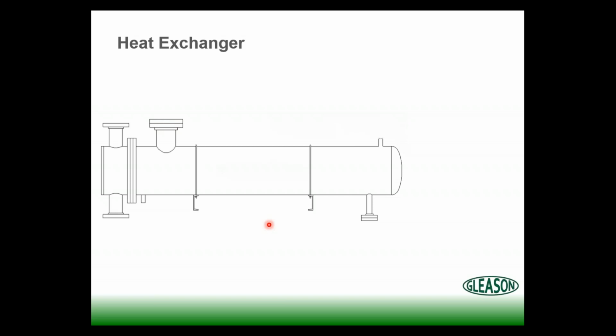If we hold liquid in that shell of that heat exchanger, two negative things can happen. Right there at the liquid-air interface on that copper bundle, carbonic acid corrosion can pit out that bundle and cause a lot of problems, causing it to prematurely fail. And when we bring steam back to it, if we're holding water in that shell, then we can hammer that bundle and do a lot of damage. That's what the photo was you saw a few minutes ago. So what do we do there?